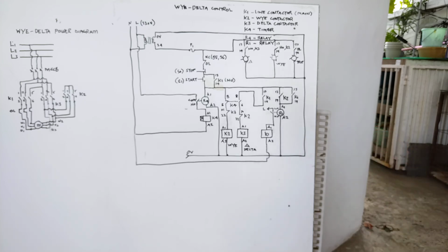So in Y, line 1, meaning K1, the timer, and K2 are energized. In delta, K1, K3, and K4 are energized. So that is how this control works.